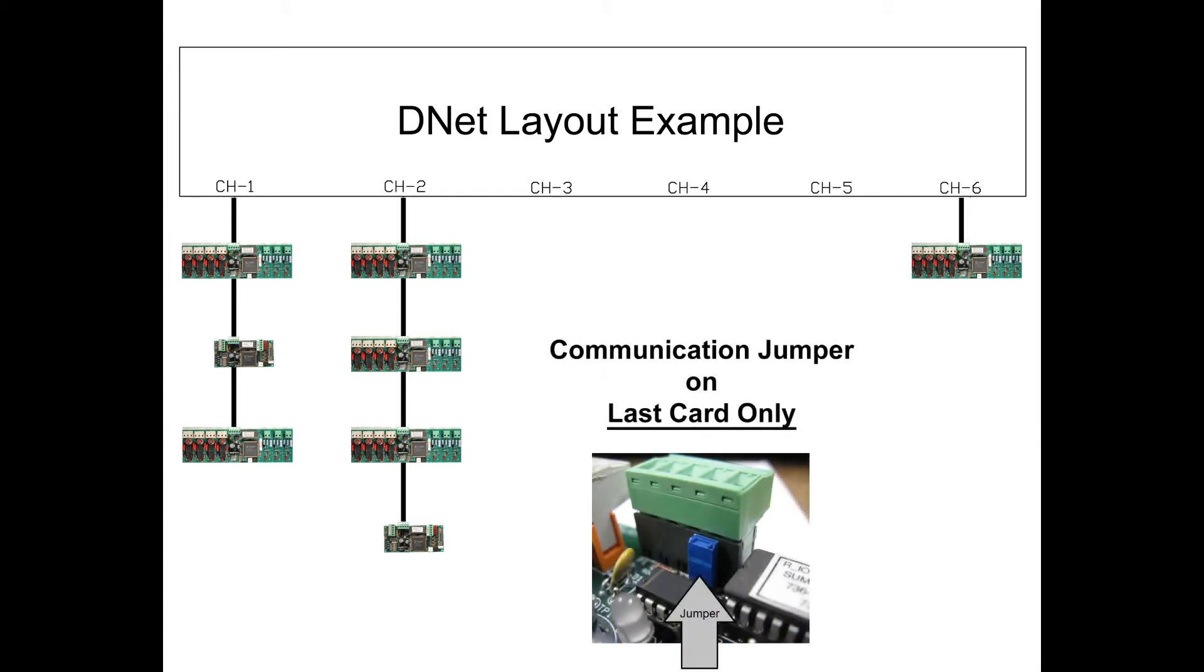Each card has a communication jumper next to the communication plug. This jumper enables a communication terminating resistor on the card. Only the last card on each string should have the jumper on.